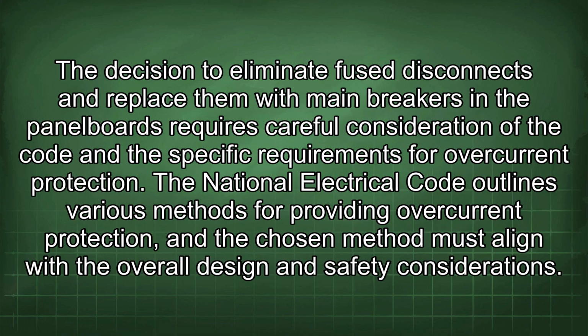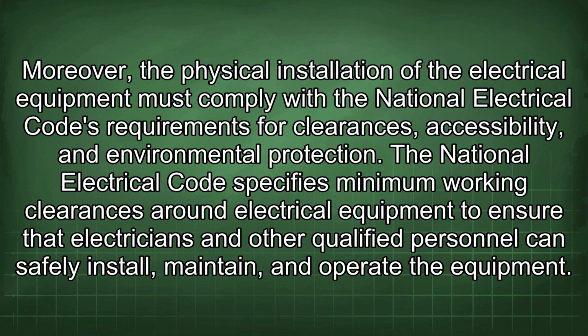The decision to eliminate fused disconnects and replace them with main breakers in the panel boards requires careful consideration of the code and the specific requirements for overcurrent protection. The National Electrical Code outlines various methods for providing overcurrent protection, and the chosen method must align with the overall design and safety considerations. Moreover, the physical installation of the electrical equipment must comply with the National Electrical Code's requirements for clearances, accessibility, and environmental protection.